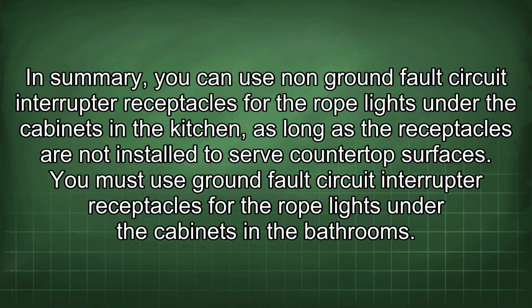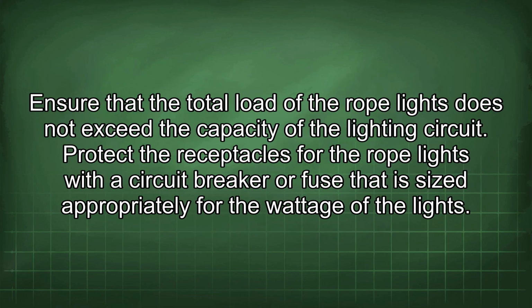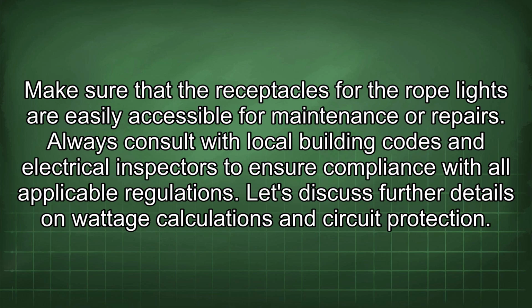You must use ground fault circuit interrupter receptacles for the rope lights under the cabinets in the bathrooms. Ensure that the total load of the rope lights does not exceed the capacity of the lighting circuit. Protect the receptacles for the rope lights with a circuit breaker or fuse that is sized appropriately for the wattage of the lights. Make sure that the receptacles for the rope lights are easily accessible for maintenance or repairs. Always consult with local building codes and electrical inspectors to ensure compliance with all applicable regulations.